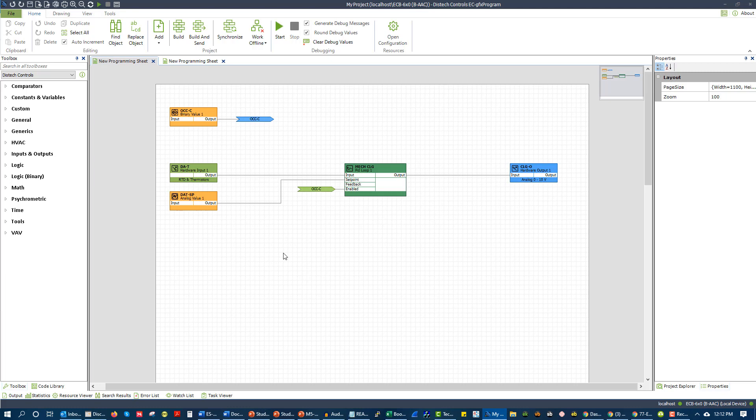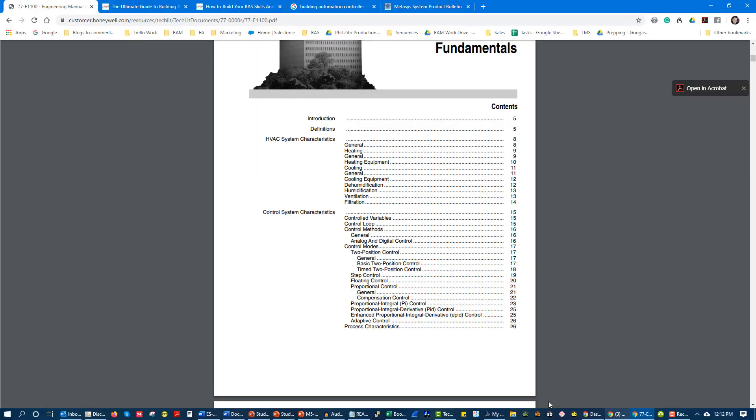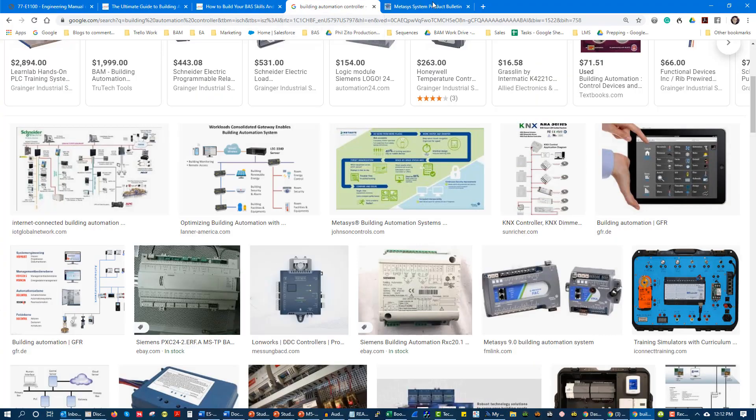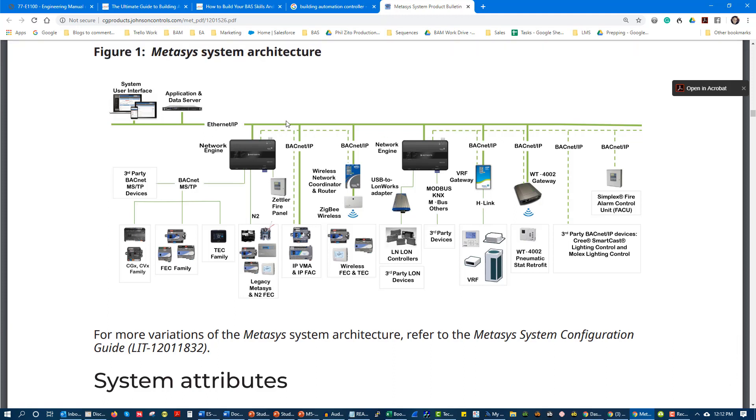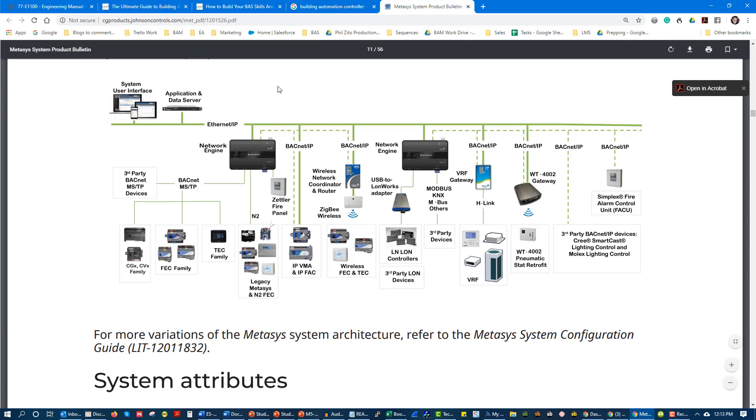That's all well and good that you could program these DDC systems. Problem was we had no way of really taking this data out of the controller and putting it on a screen like you're seeing right now so someone could actually do something with it. That's where these supervisory devices came in. You may have heard network engines, Java application control engines, JACEs, web supervisors - whatever you've heard, the main purpose of supervisory devices originally was to take data from field controllers and put it into a thick client, a stationary desktop that could display data from the field controllers and allow the building operator to interface. This was a big deal - this didn't exist before. You actually had to go and read gauges, change things in your pneumatic system. You didn't have these capabilities.